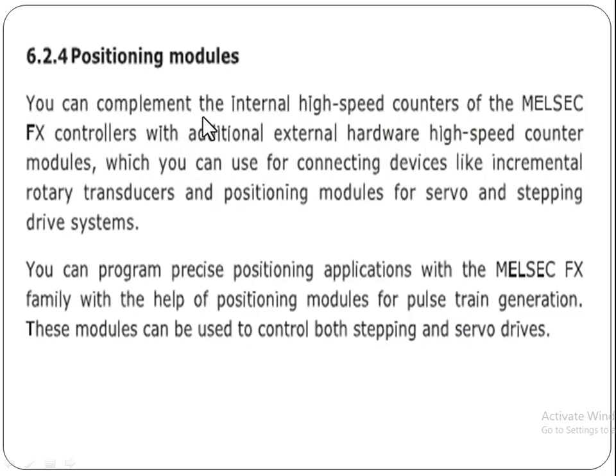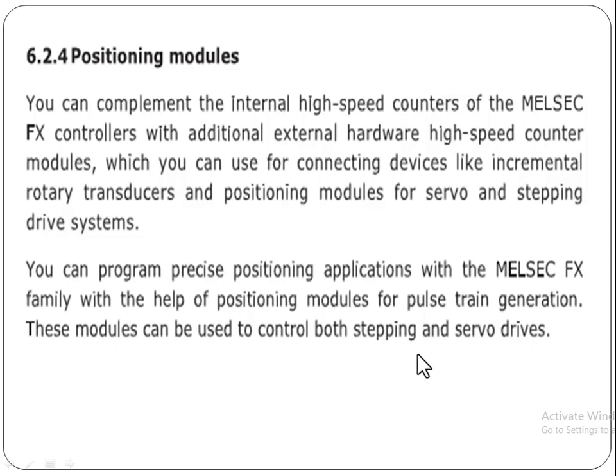The third type is positioning modules. You can complement the internal high-speed counters of the Mitsubishi FX controllers with additional external hardware high-speed counter modules. These are used for generating different kinds of pulses for connecting devices like incremental rotary transducers, and positioning modules for servo and stepping drive systems. You can program precise positioning applications with the Melsec FX family using positioning modules for pulse generation, to control both stepping and servo drives.